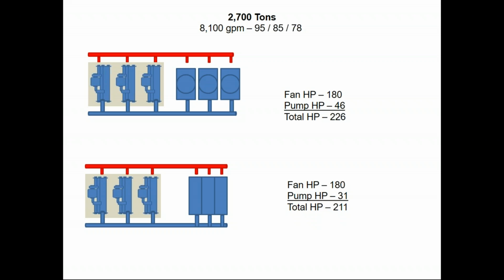On our TowerTech system, our fan horsepower is 180, similar to conventional. But because we operate with less head, we're at 31 horsepower. So we have a total horsepower advantage on design day of 7. That's not very significant, but we have a 7% advantage on design day. Part load is where we see the significant advantage.